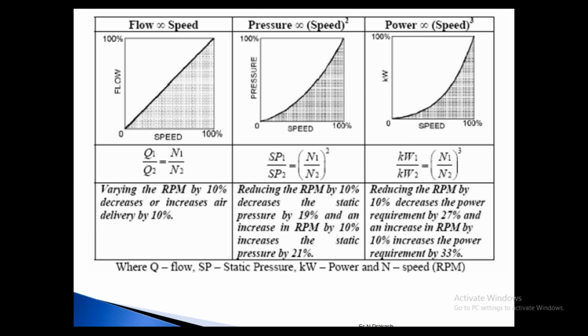Whereas the pressure is the square of the speed. The pressure will increase or decrease with the square of your speed. That is the fan characteristic. Whereas power is the cube of your speed. This is a square and this is a cube. This is the fan law. Everybody must be knowing this; if not, that is the reason I explained. So not only the fan selection, best efficient fan, but also the speed at which the fan is working matters. It will deliver only at a particular speed, which means you have to run at that particular speed.